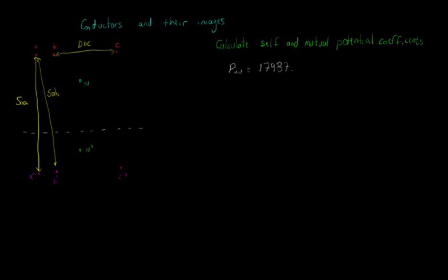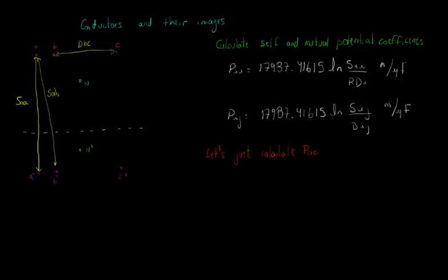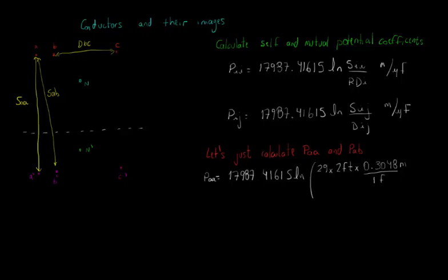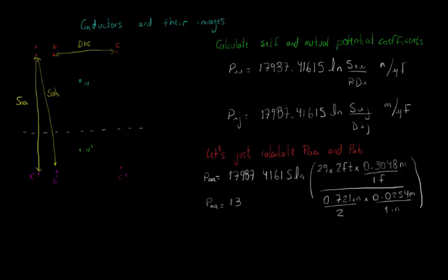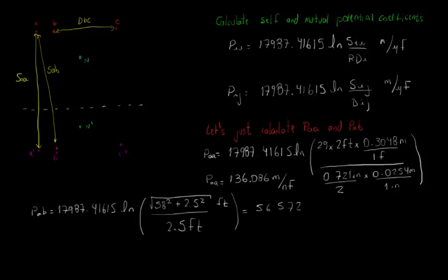The self and mutual potential coefficients are calculated according to the following expressions, where RDI is the radius of conductor I. Notice that the unit is meters per microfarad. As an example, let's calculate the self potential coefficient of phase A, PAA, and the mutual potential coefficient between phases A and B, PAB. Be careful to adjust the distances for the same unit.